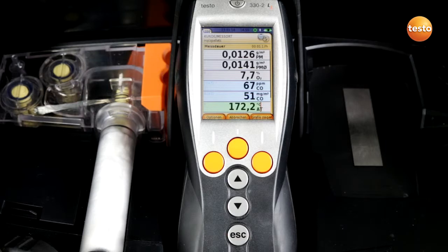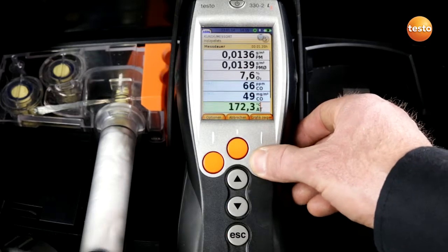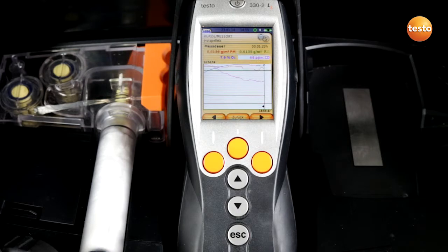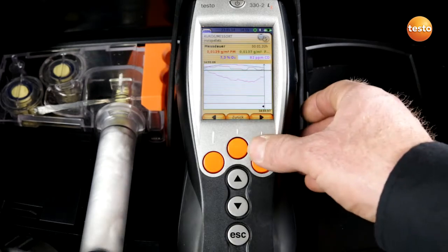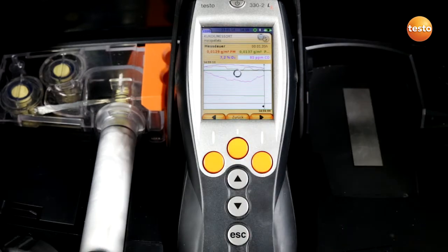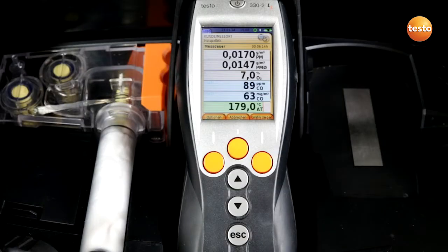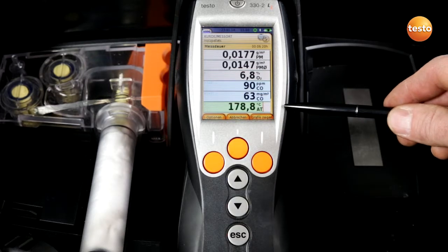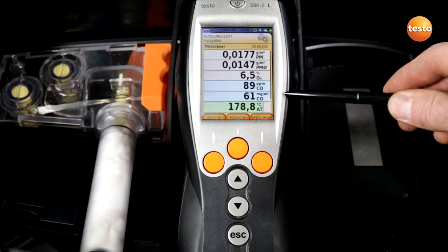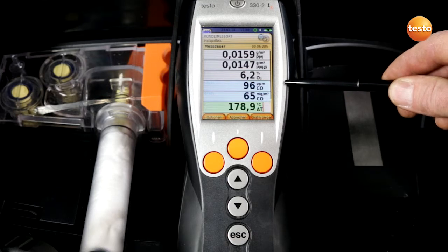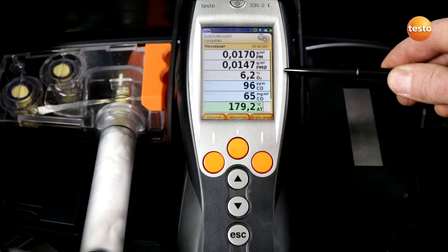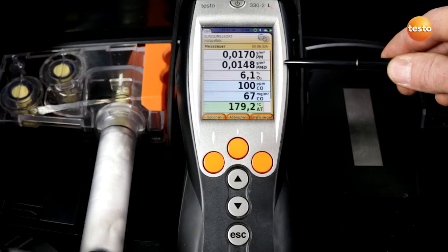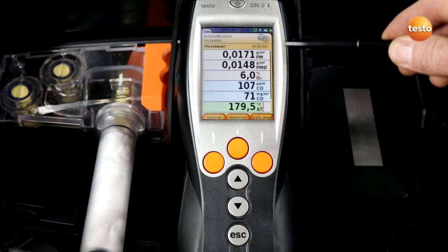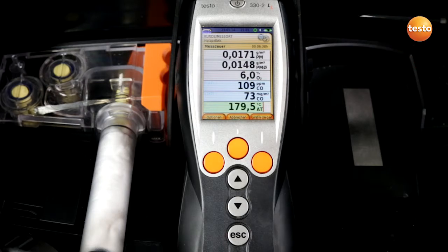During the 15-minute measurement, we have the possibility of viewing the combustion behavior in the graphic display. I return to the measurement values here. We can now see the current values in the display. At the bottom is the flue gas temperature. After that, the CO content in milligrams per cubic meter, the CO content in ppm, the oxygen content in percent, and the mean particle value in grams per cubic meter. In the top line is the current fine particle content.